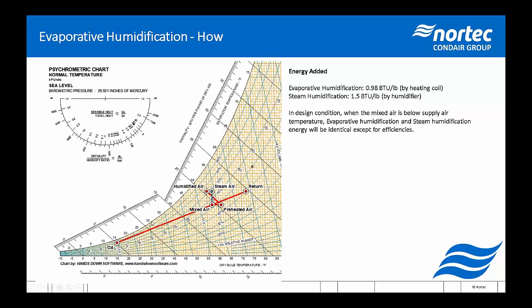So we have effectively the same mixed air return air point because it is the minimum amount of outside air we can bring in, and we're in heating mode. So we have to heat that up in order to get to a point at which we can evaporate water in the air and land at 55 degrees, because that's our goal supply temperature here. So this would be done with a gas heating coil, hot water coil, or electric heat, typically.